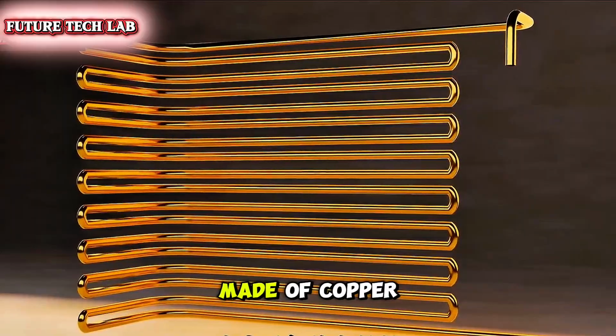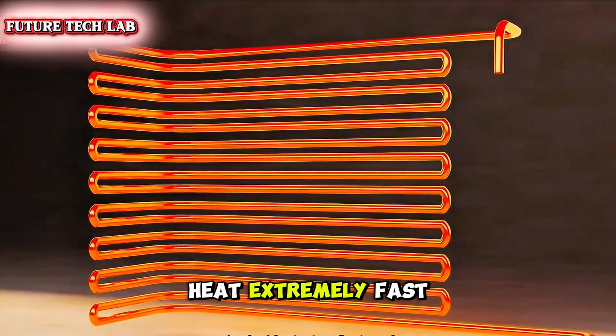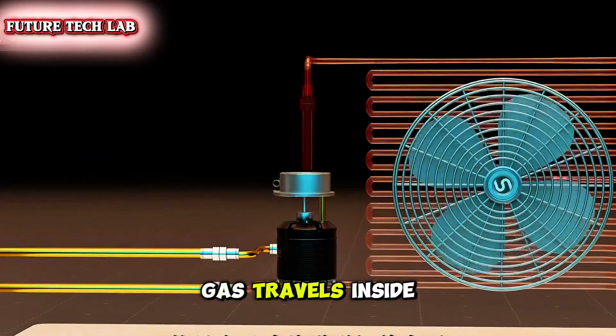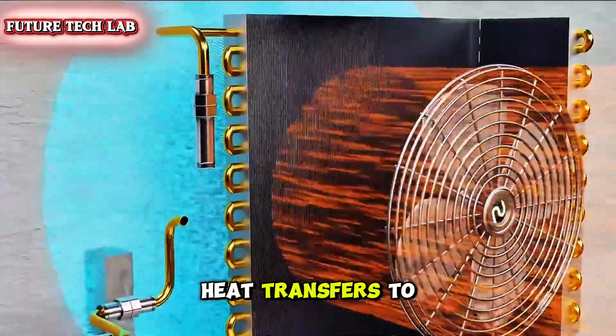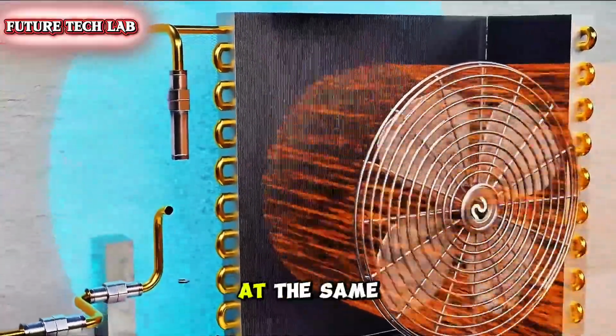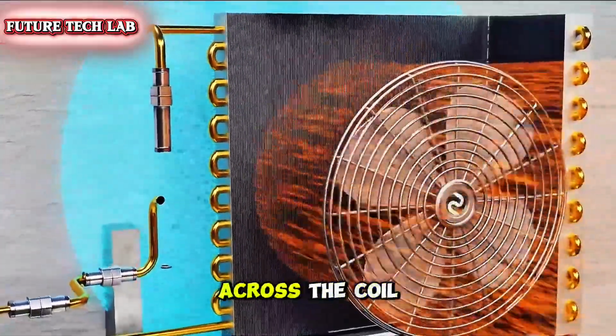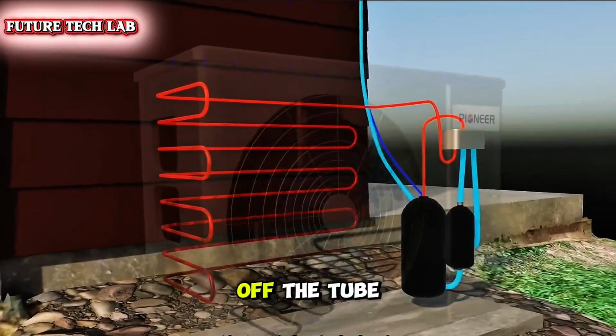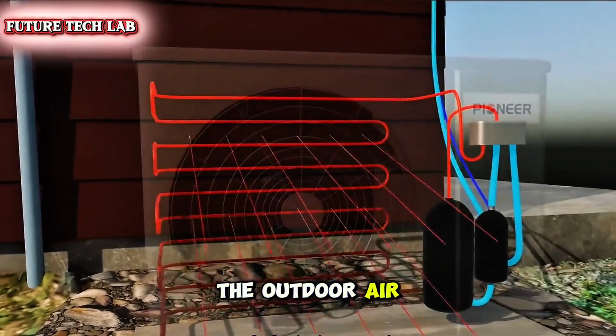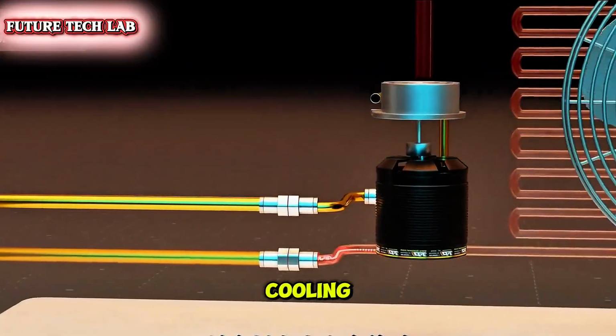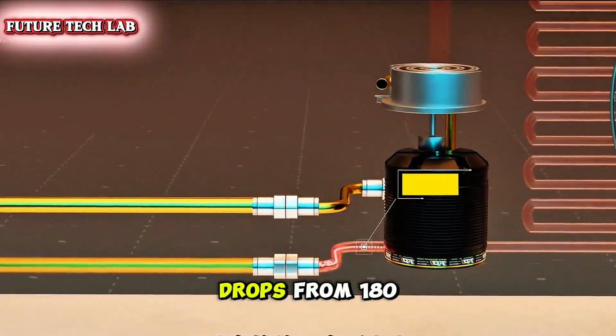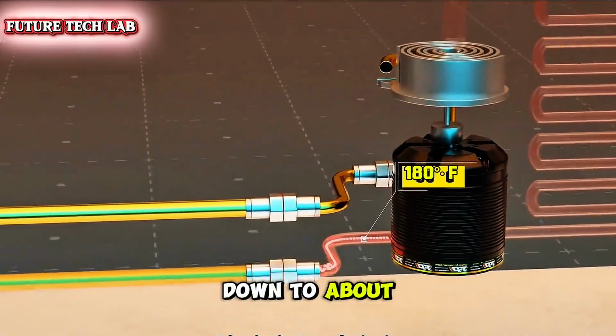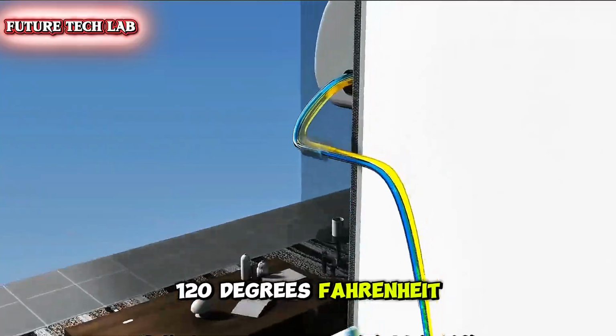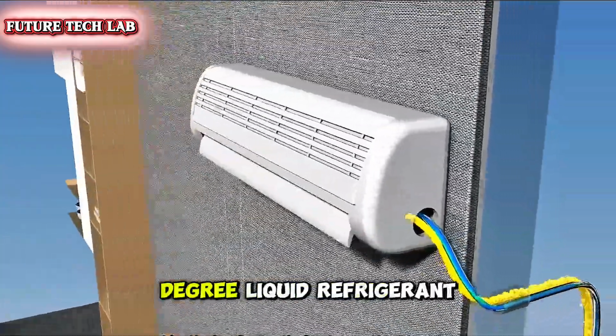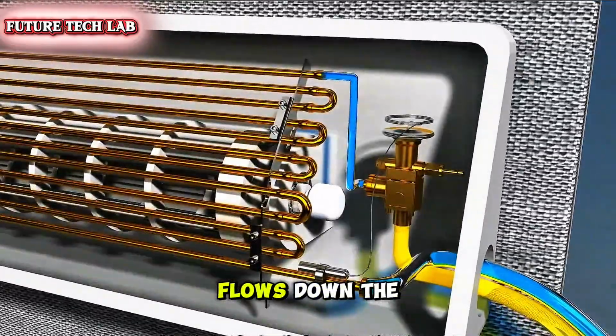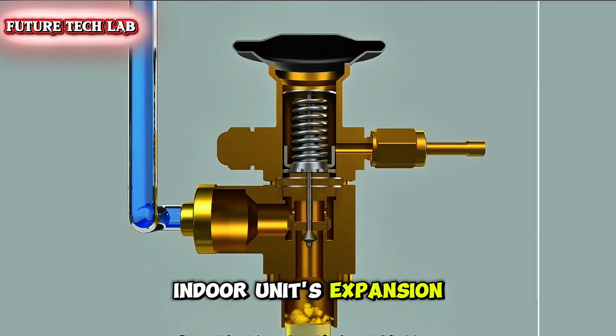The condenser is made of copper tubes that conduct heat extremely fast. As the hot gas travels inside the long coil, heat transfers to the surface of the copper tubes. At the same time, the outdoor axial fan blows across the coil, forcing the heat off the tube walls and into the outdoor air. After this wave of physical air cooling, the refrigerant temperature drops from 180 degrees down to about 120 degrees Fahrenheit. Next, this 120-degree liquid refrigerant flows down the pipe straight into the indoor unit's expansion valve.